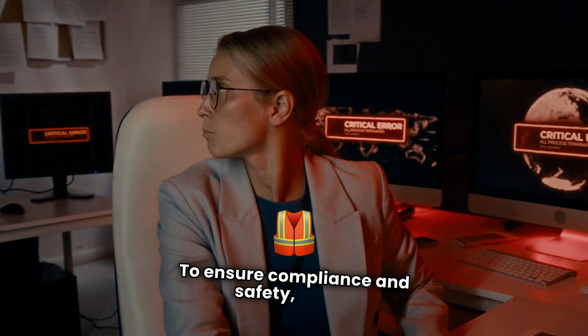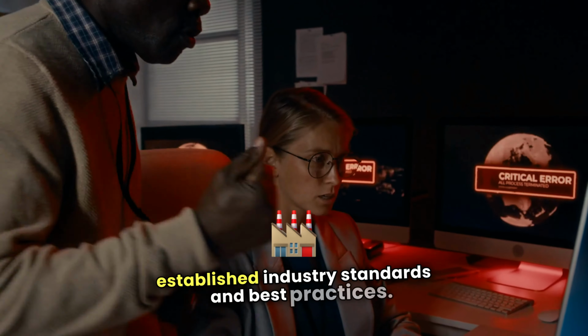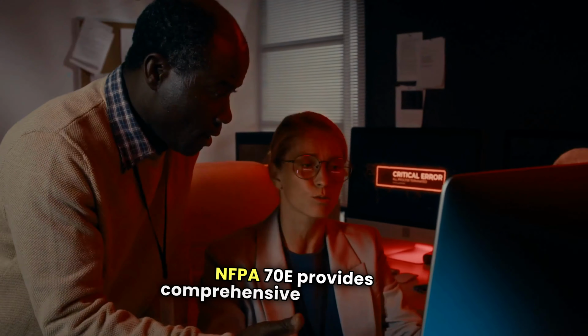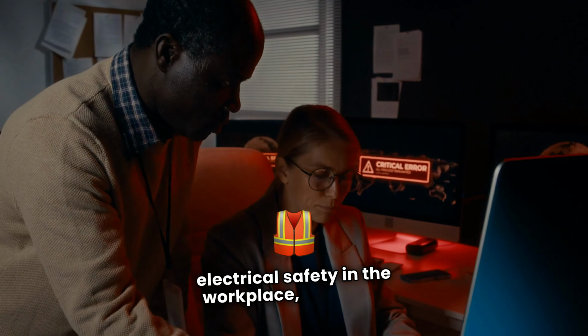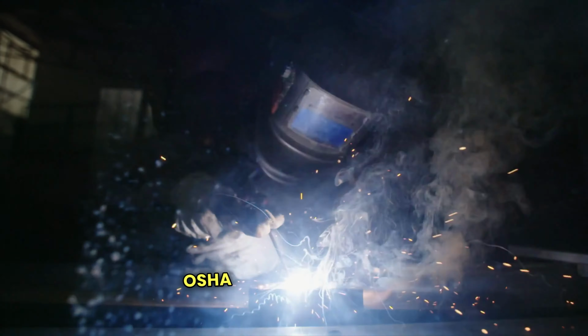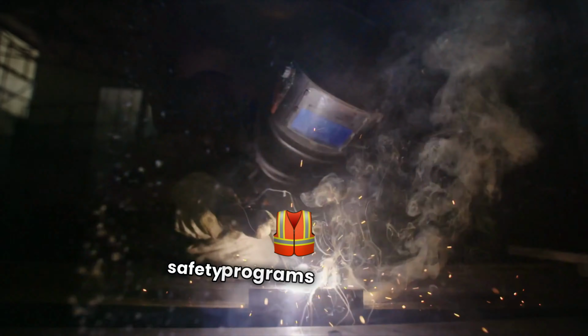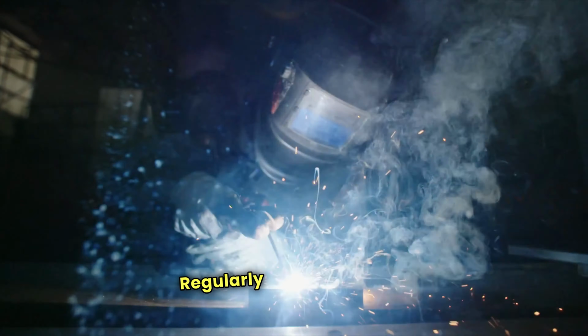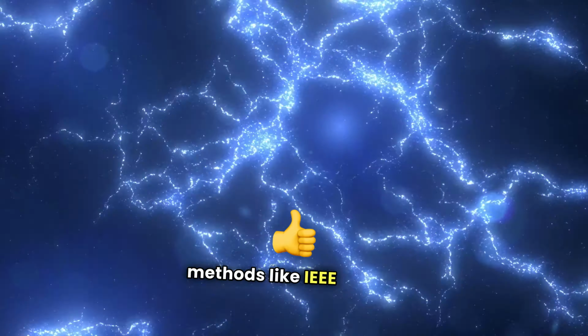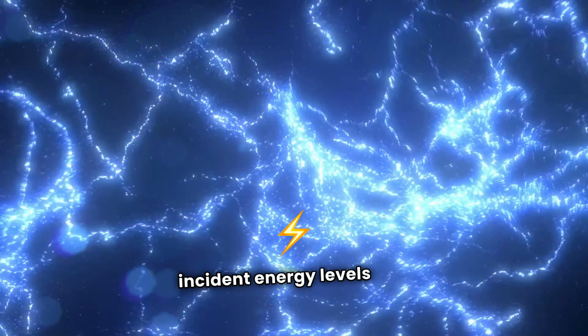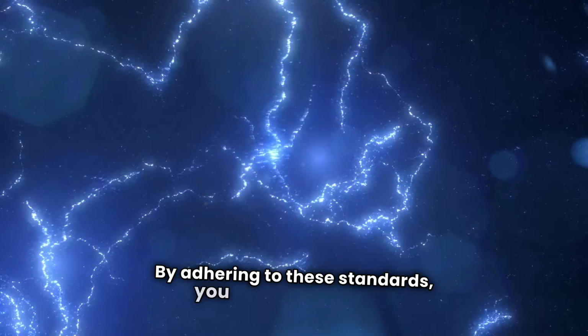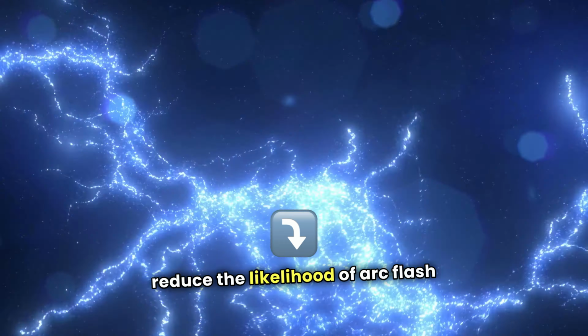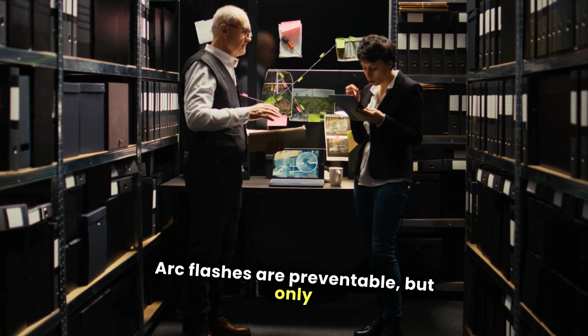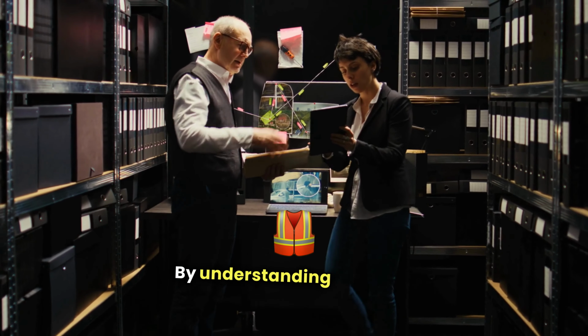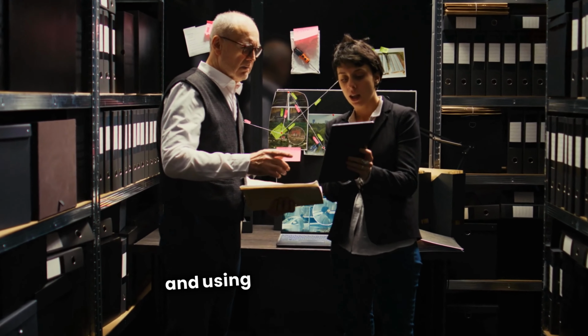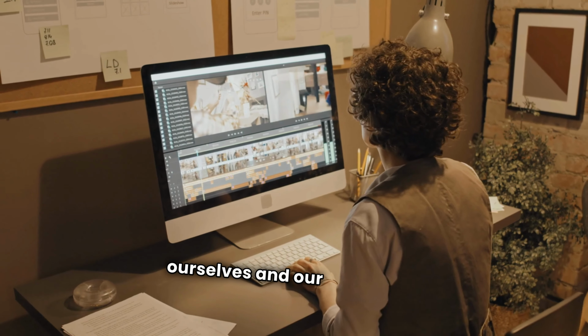To ensure compliance and safety, follow established industry standards and best practices. NFPA 70E provides comprehensive guidelines for electrical safety in the workplace, including arc flash risk assessments. OSHA regulations require employers to implement safety programs and provide adequate PPE. Regularly assess arc flash hazards using methods like IEEE 1584 to determine incident energy levels and boundaries. By adhering to these standards, you can significantly reduce the likelihood of arc flash incidents. Arc flashes are preventable, but only if we take the necessary precautions. By understanding the risks, implementing safety measures, and using proper PPE, we can protect ourselves and our colleagues from harm.